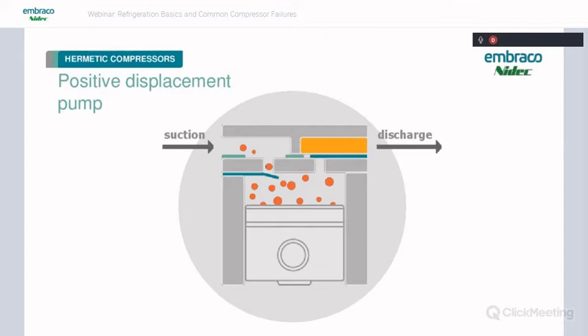If we bring in a slug of liquid to this pump, it's going to try to compress it, and it's going to cause catastrophic damage in the form of bent or broken suction or discharge valves, blown out suction or discharge gaskets. If we get enough liquid in there, we could even blow a hole in the piston or break a connecting rod, cause major damage like that. So you can see extremely high pressures inside this cylinder, in the neighborhood of 3,000 psi, if you pull liquid in there. So that's why we cannot have liquid in a positive displacement pump. Always want to protect these types of compressors from liquid floodback or slugs.